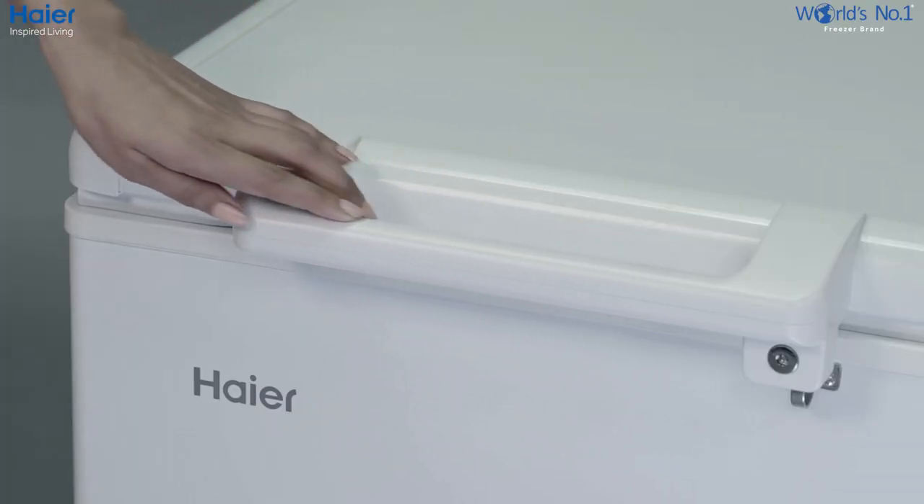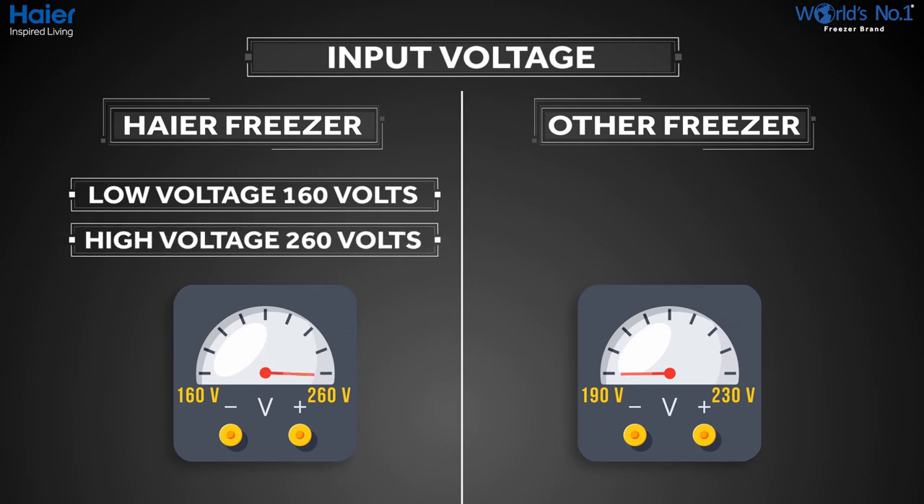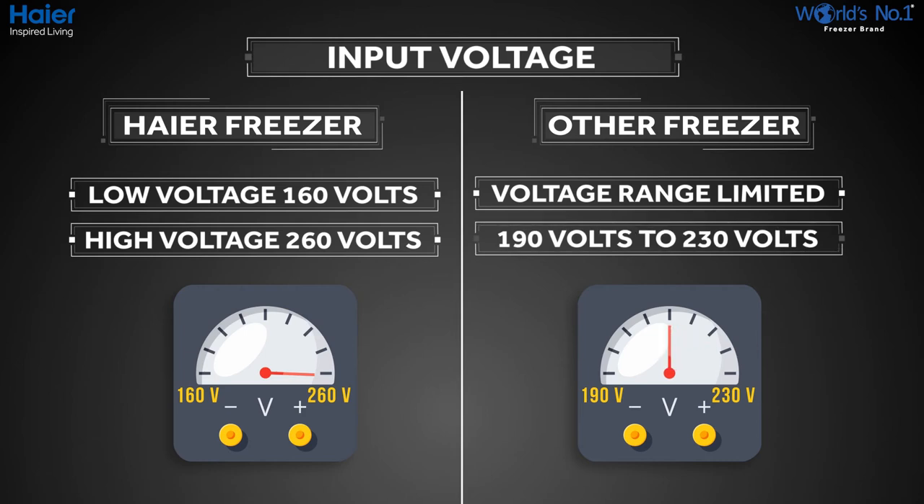This convertible model of deep freezer is designed to start at an input voltage of as low as 160 volts and as high as 260 volts, adapting to irregular power supply and voltage fluctuations. Haier freezers can run on a wide range of voltage inputs, making them lesser dependent on stabilizers for operation. For other freezers, the voltage range is limited from 190 volts to 230 volts.